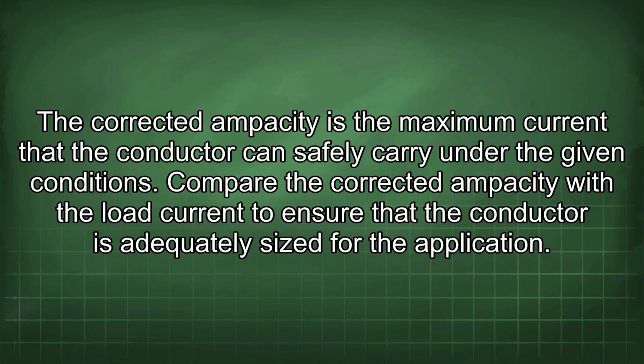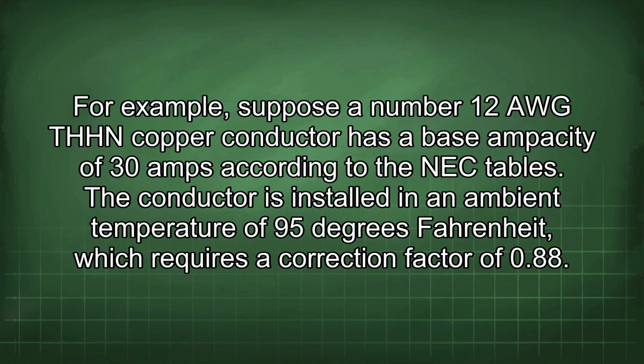The corrected ampacity is the maximum current that the conductor can safely carry under the given conditions. Compare the corrected ampacity with the load current to ensure that the conductor is adequately sized for the application. For example, suppose a number 12 AWG THHN copper conductor has a base ampacity of 30 amps according to the NEC tables. The conductor is installed in an ambient temperature of 95 degrees Fahrenheit, which requires a correction factor of 0.88.